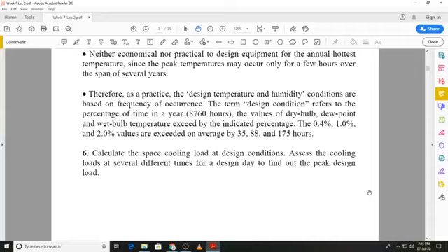When we say the frequency of occurrence, we are saying, let's say if we select the outside design temperature at 0.4% frequency of occurrence, it means that of a total of 8,760 hours in a year, it is possible that 0.4% of the times, that is 35 out of 8,760 hours, the outside temperature may be higher than the temperature that we selected. But 99.6% of the times our plant will give us the desired service in terms of the load that we have.